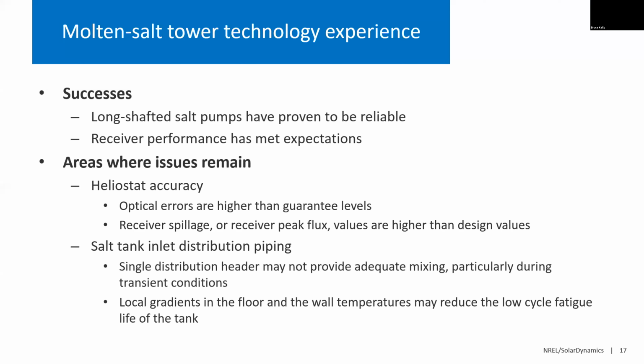Regarding the salt tanks, there have been sort of 3 problems. One is how the flow is distributed when the flow enters the tank, particularly in the hot salt tank. Most of these projects use a single ring header near the bottom of the tank, and that's where the flow is introduced. But these tanks are large. 40 meters is a typical value. And so as you're introducing flows into the tank, you don't wind up with an isotropic distribution of temperatures within the tank. You wind up basically with temperature gradients.